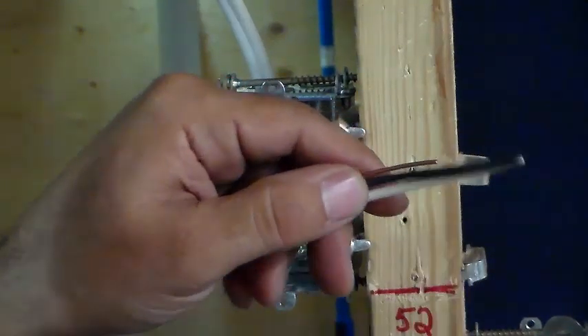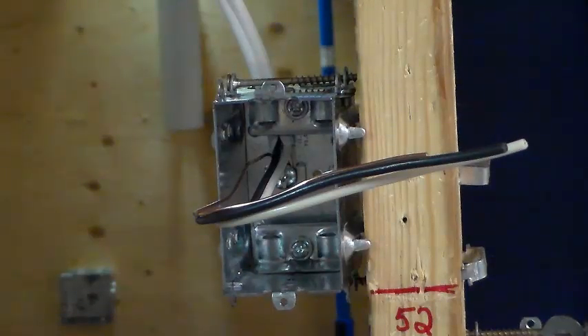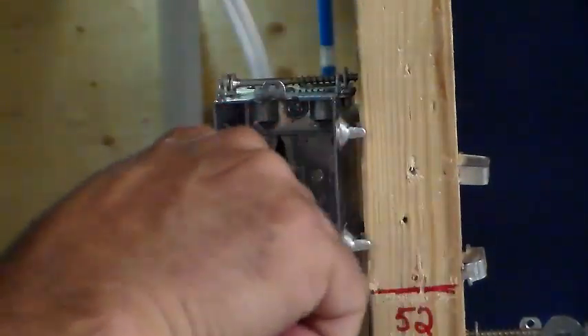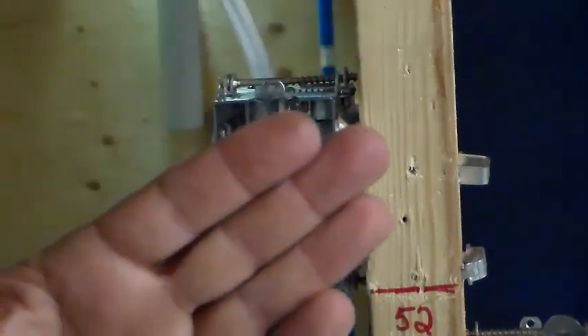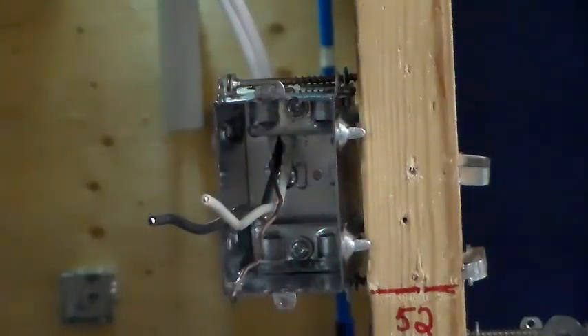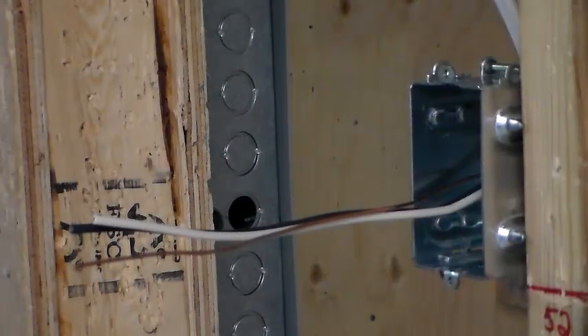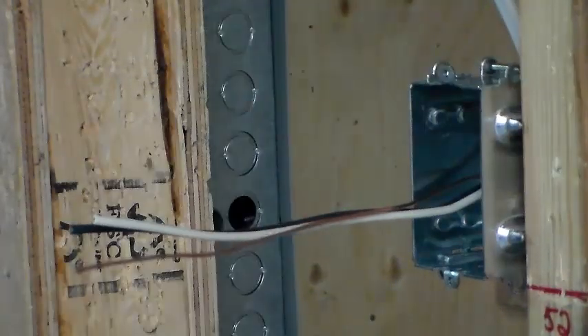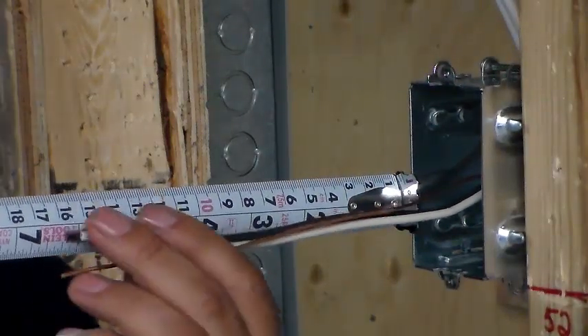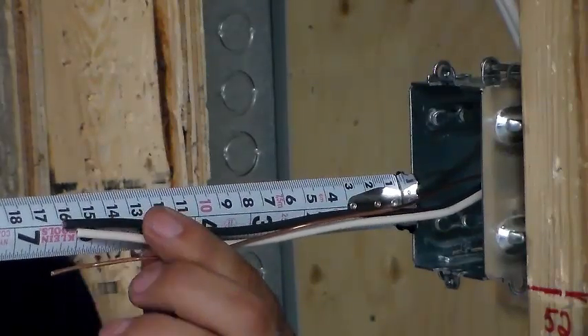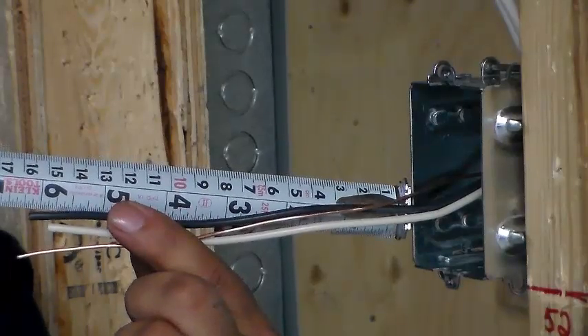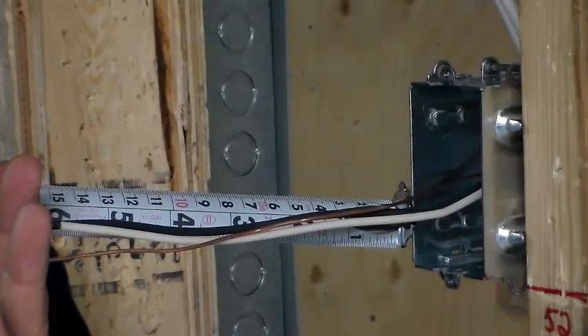So what I usually do is I like to trim them all the same length so that when making the connection to your plug, they all look and connect very evenly. So I'll trim those two. They're all the same. And now if I were to measure from the edge of the box to the end of my cables, I should have six inches. Okay, we've repositioned the camera now so I can get a better view of the length of the cable. Remember that the code requires six inches from the edge of the box. There will be drywall here so all you're going to see is the edge of this box at the drywall. So we take a tape measure and we put it there. You'll notice that we are roughly at six inches. And that's the minimum amount of wire required as per code. I could have eight. I could have nine. But I have to have six. That is the minimum code requirement.